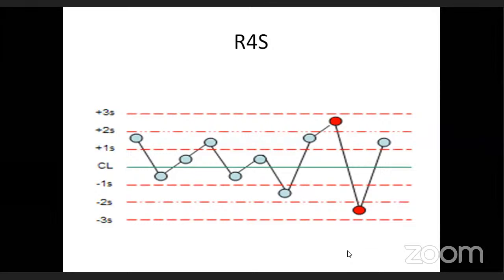And the preparation of the calibration is also important. Has the calibrator been prepared properly? Does it belong to the same lot as in the system, as in the machine? Similarly, you also have to look at the controls in the same manner. The controls must match in the lot number in the system, in the machine, and their preparation should have been done properly, and the shelf life should not be expired.